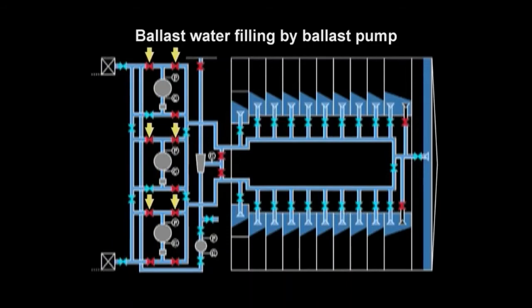Centrifugal pumps are commonly used as ballast pumps. Start the pump with its discharge valve fully closed to avoid an overload at the start of the pump and to minimize surge pressure.